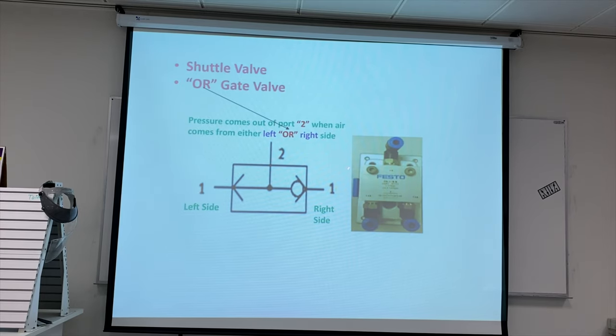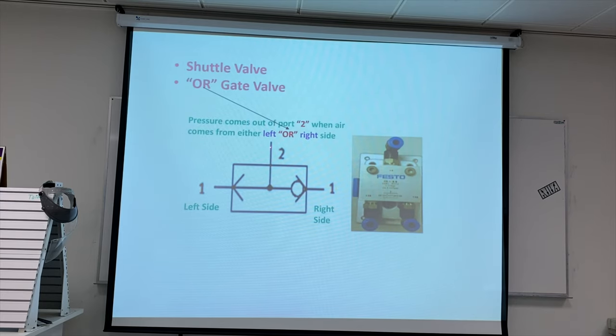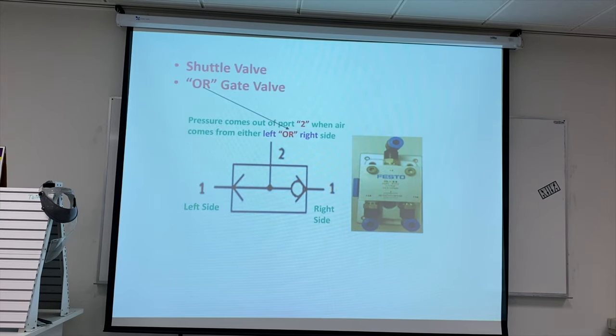Next we have the shuttle valve, also called the OR gate. In the shuttle valve, only one side needs air to enter. If air enters from the left side, it activates output port 2. Similarly, if air enters from the right side, it also activates output port 2. This is the shuttle valve symbol and its position.